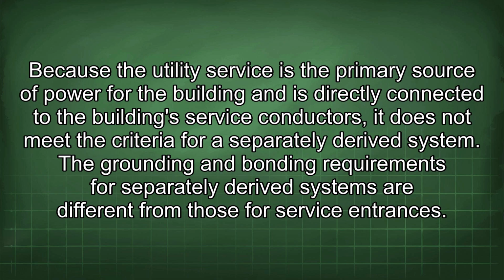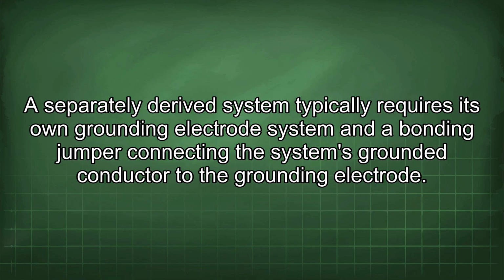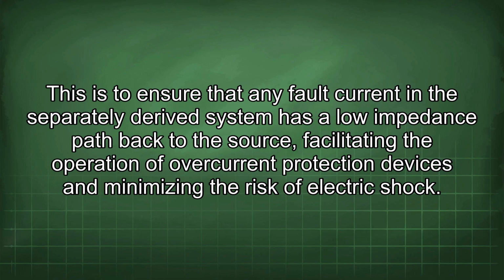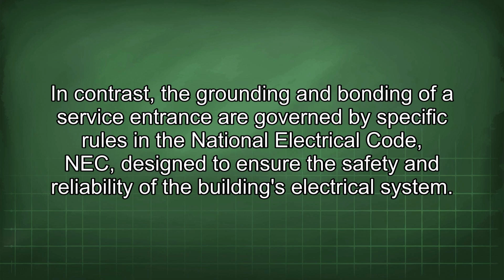The grounding and bonding requirements for separately derived systems are different from those for service entrances. A separately derived system typically requires its own grounding electrode system and a bonding jumper connecting the system's grounded conductor to the grounding electrode. This is to ensure that any fault current in the separately derived system has a low impedance path back to the source, facilitating the operation of overcurrent protection devices and minimizing the risk of electric shock. In contrast, the grounding and bonding of a service entrance are governed by specific rules in the National Electrical Code (NEC), designed to ensure the safety and reliability of the building's electrical system.